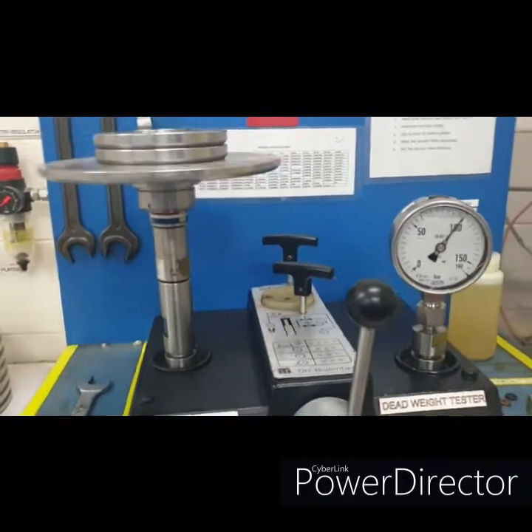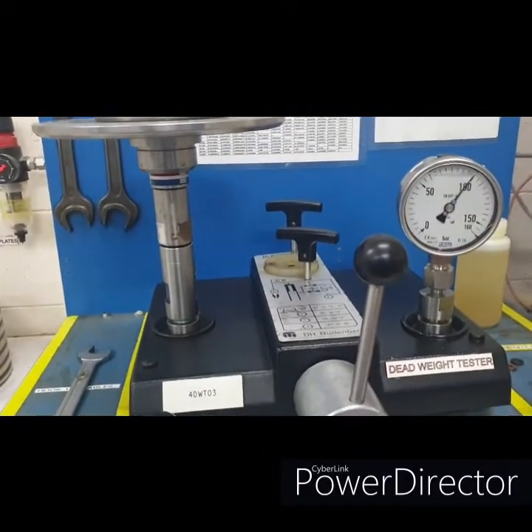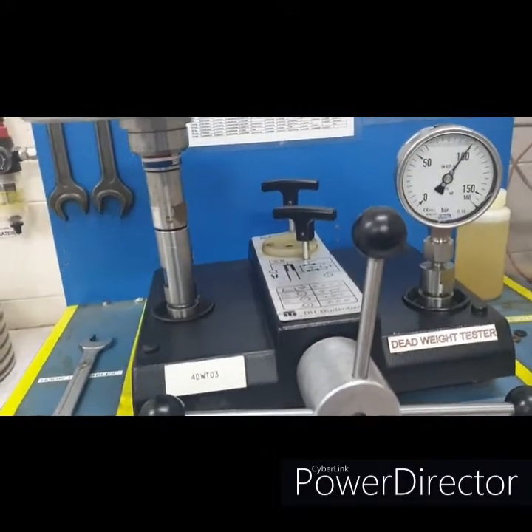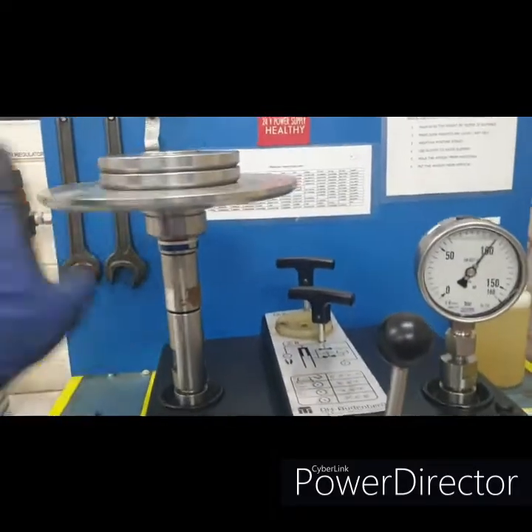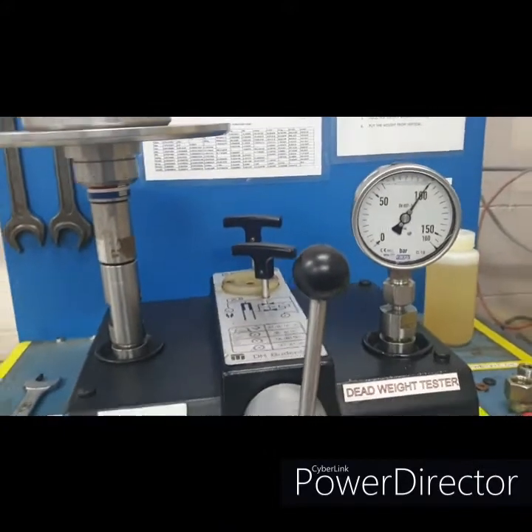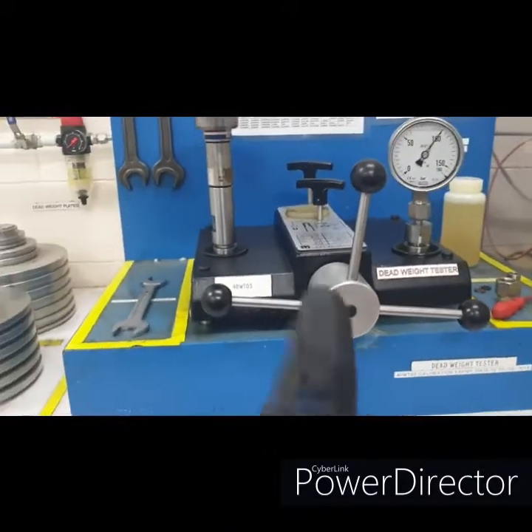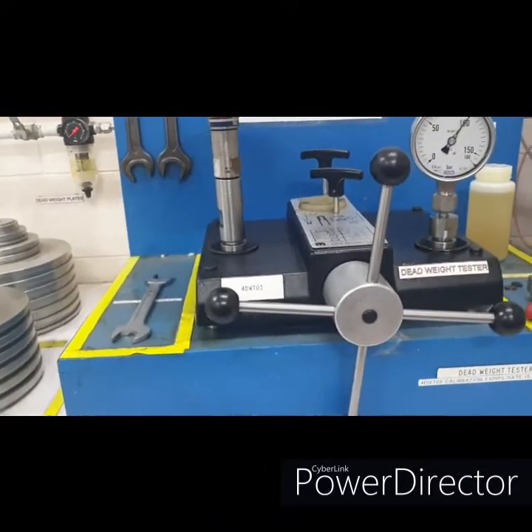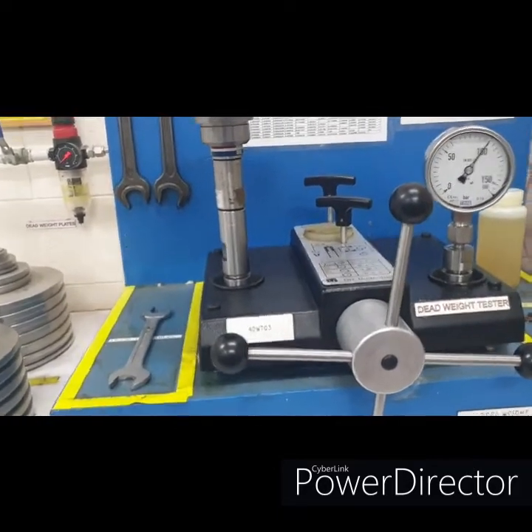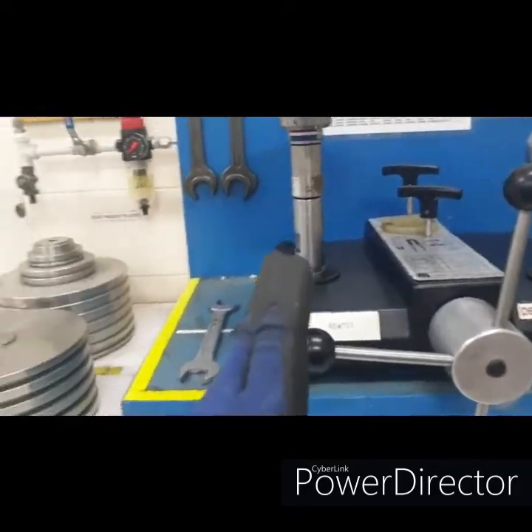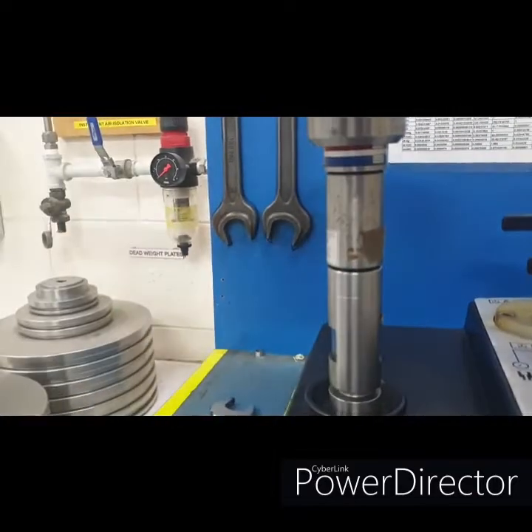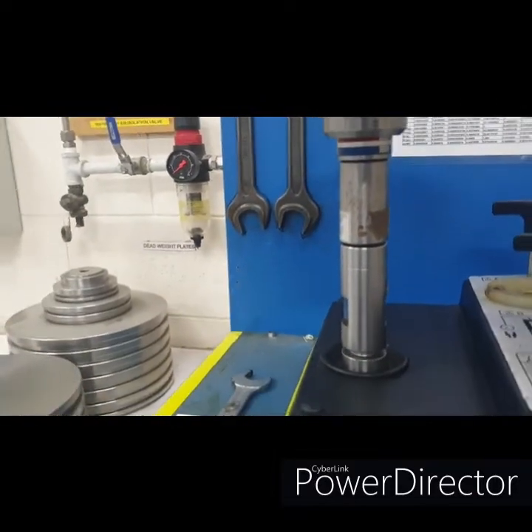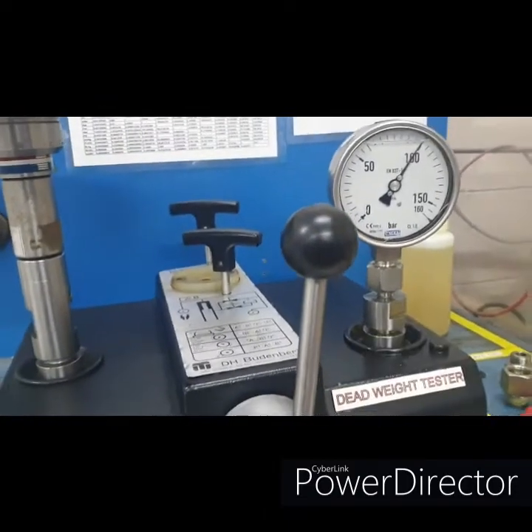So you just spin it. Now another, it's just a tip. You just spin it for a while and look for the pressure. Do not touch the hand pump. Now observe whether the pressure is getting down and the floating indicator also is reducing or not. If it is reducing and the pressure is getting down, that means there is a leak somewhere.